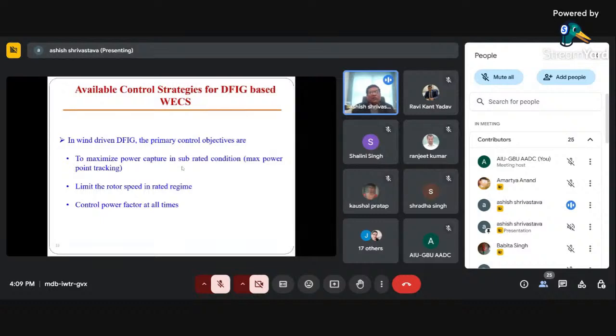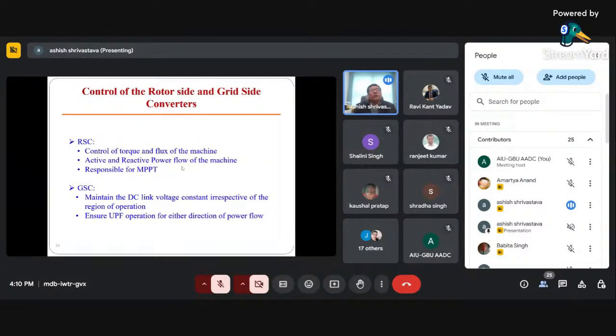So what are the available control strategies in wind driven DFIG? The primary control objective is to maximize the power capture in sub-rated condition by using maximum power point tracking. It is best suited with DFIG, with maximum power tracking for all variation of the speed from lower to higher. Limit the rotor speed in the rated regime. You can control the rotor speed because you can flow the power in either direction, from rotor to grid or grid to rotor. So you can limit the rotor speed, and you can control the power factor at all times. You can have full control on the power factor and THD for large variation on either side of the speed, so that is for the large variation of the wind speed. So this is the advantage.